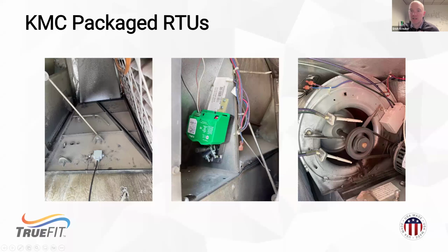It was tied and geared to the OA damper. We have a modulated actuator controlling that mixed air damper assembly. And then on the right, you see a pitot array, again, getting that fan inlet total supply air there.